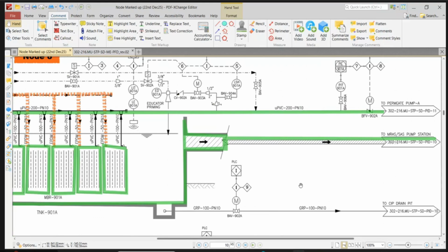For example, you will see on the SCADA system up to minus 0.6. That means the performance of the membrane is not good. So it's an earlier indication before damaging, that you should be careful. There is an issue. You have to make it clean. Okay. So yeah, that is TMP.